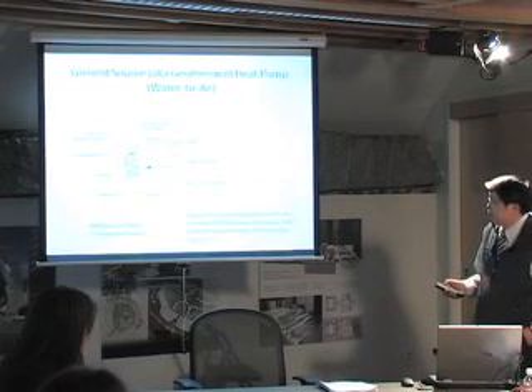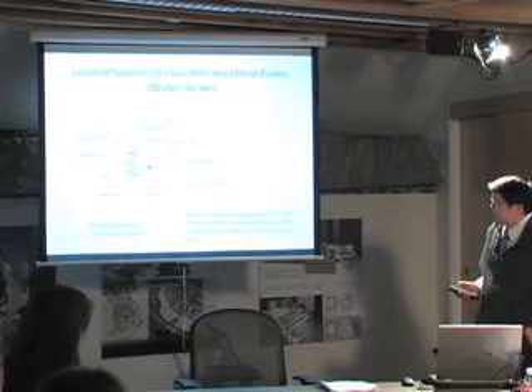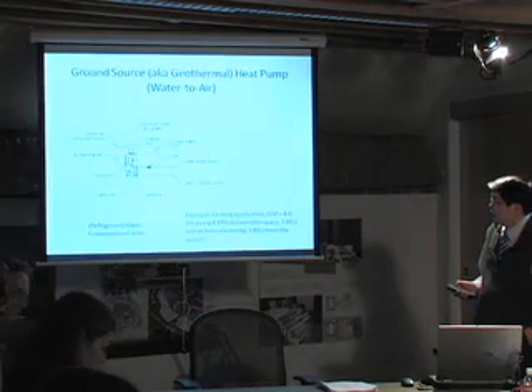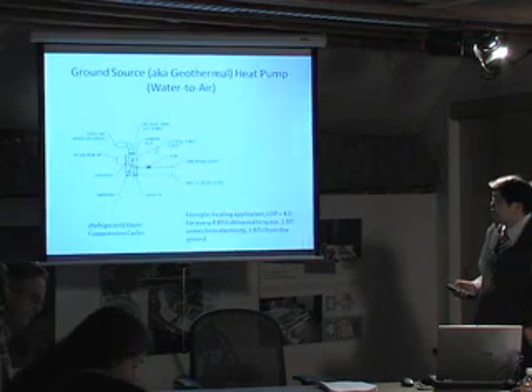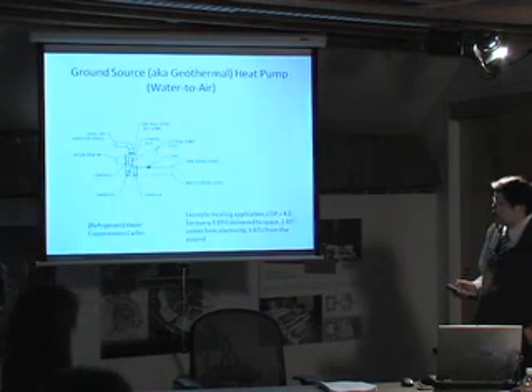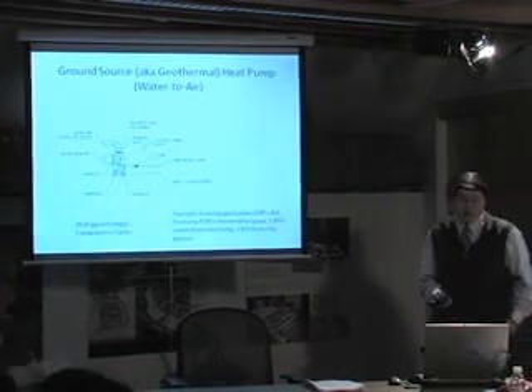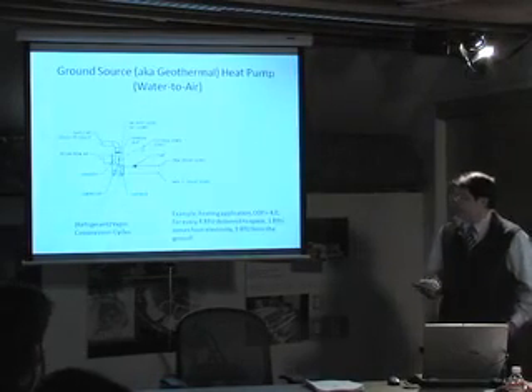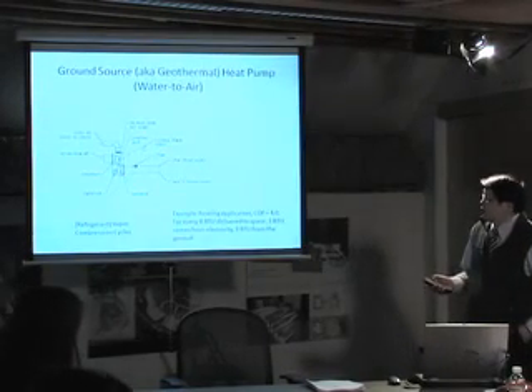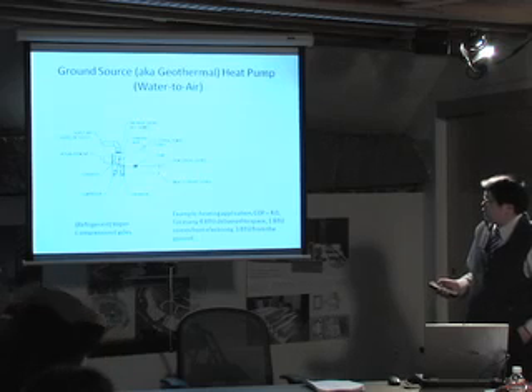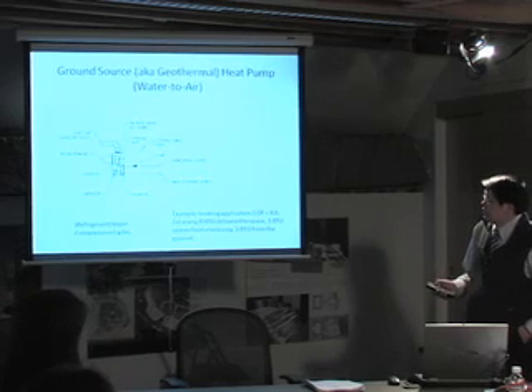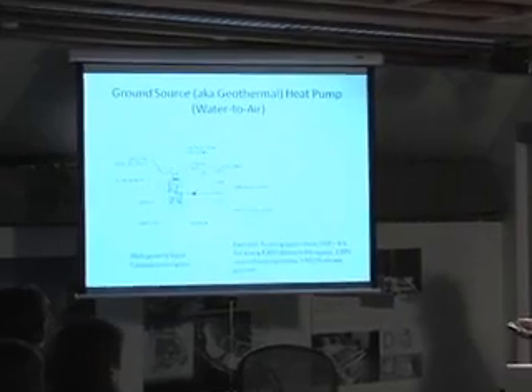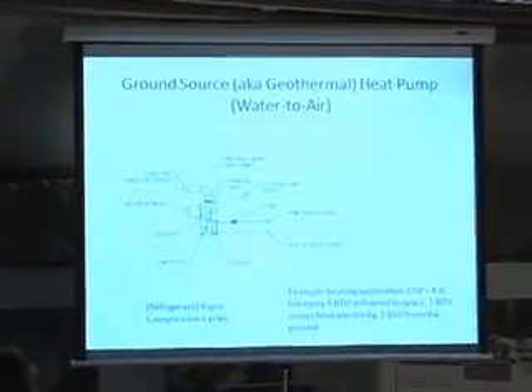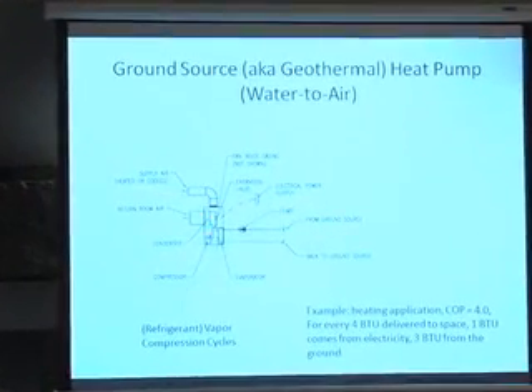You have a casing, and inside the casing you have 4 basic components: a compressor, evaporator, a condenser, and expansion valve. The 4 basic components are the same components as in a typical fridge. This is water to air, meaning you take groundwater from a ground source and pump it through the evaporator, and you produce heated or cooled air throughout the ductwork supplied to the space.